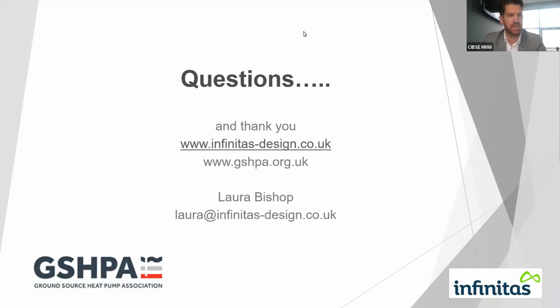Another question: are there any rules of thumb in the UK for heat from ground source loop, horizontal or vertical, in watts per meter squared of pipe run, without needing to rely on a thermal response test? Very early on in a project you do just want a rule of thumb - yes, there are resources, and if whoever's asking emails me afterwards I can point you to them. It's quite varied - you've got MCS lookup tables, mainly for anything below 45 kilowatts, so smaller domestic stuff. There are a couple of resources I can think of, but once you get anywhere near detailed design, do not use rules of thumb - that's how things go wrong. You absolutely need to engage someone who knows what they're doing with ground collectors. But yes, early on, there are resources that can give rules of thumb for different areas of the UK and different geologies.